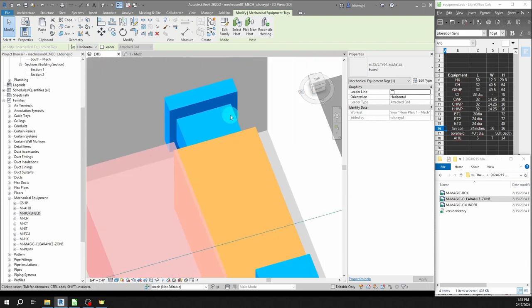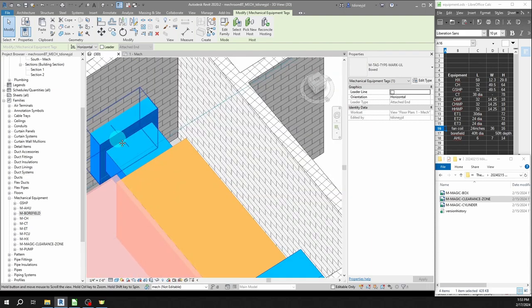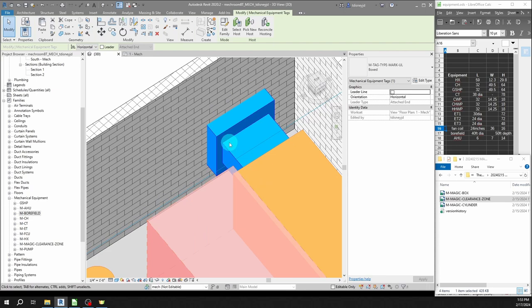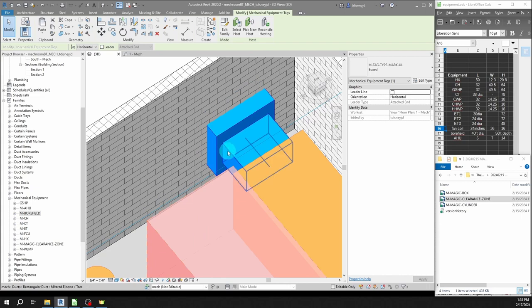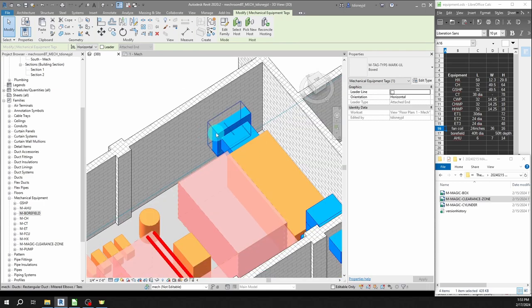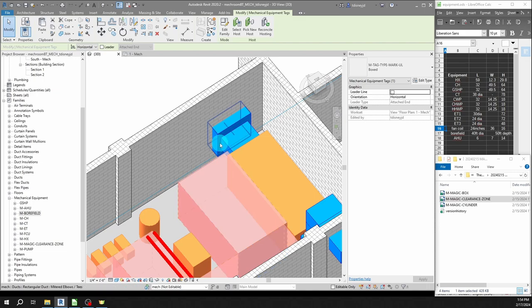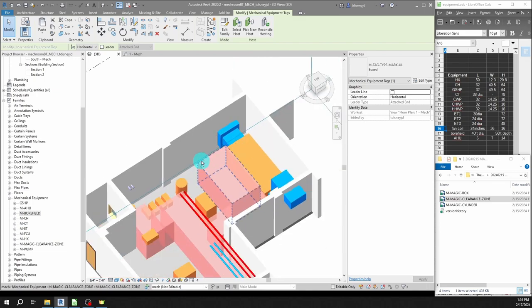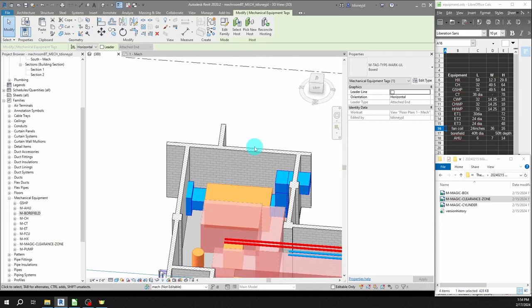You might accuse me, and it's a good point, that I did some things wrong, like this over here. Just because I didn't happen to have a fitting at the moment on hand that would make this connection to the plenum, and I didn't want to get fussy - oh I need this to connect in with the tap fitting into a different duct. No, forget it, just stick it in there. You can fuss with it later, but fussing with it now is such a waste of time. Get it done.